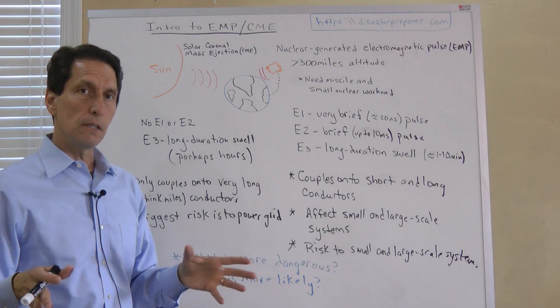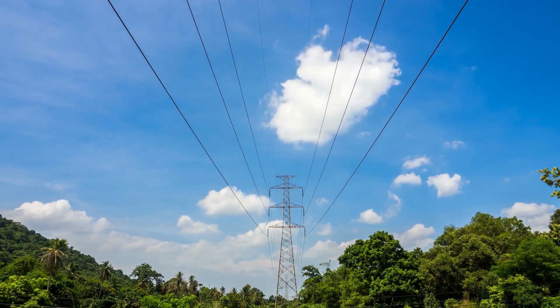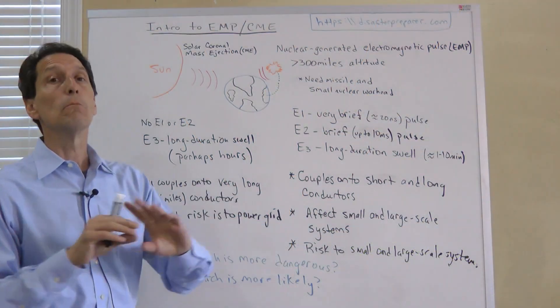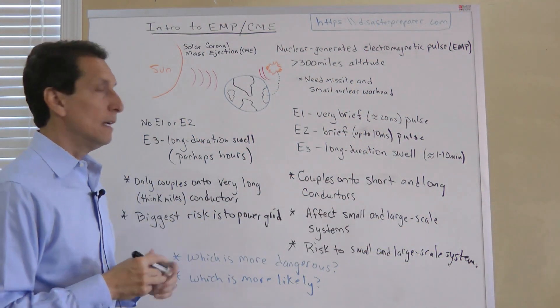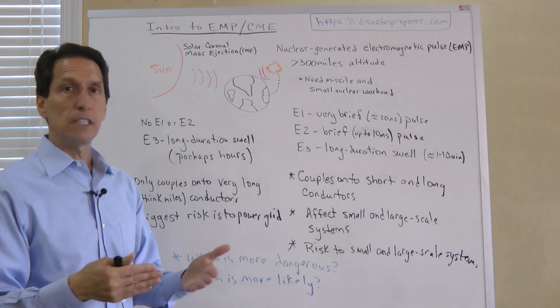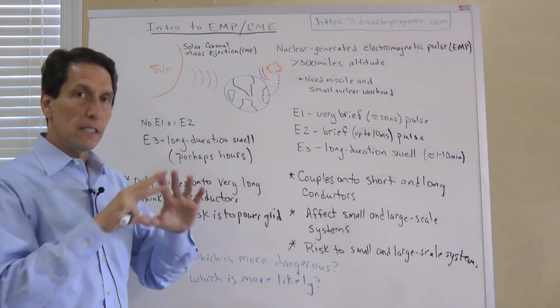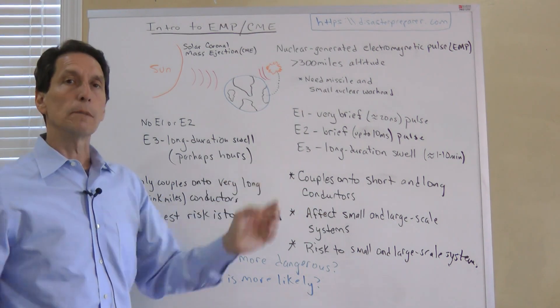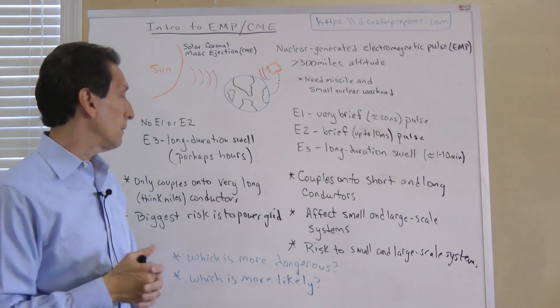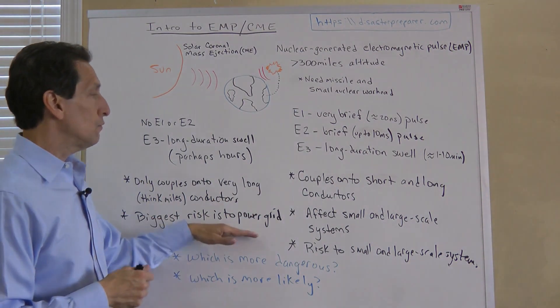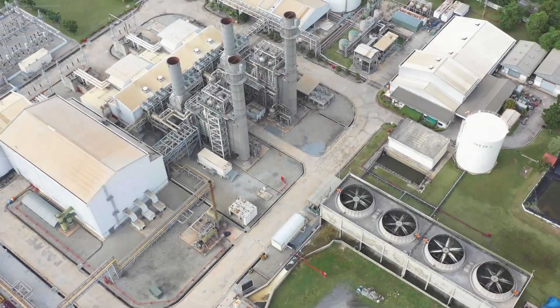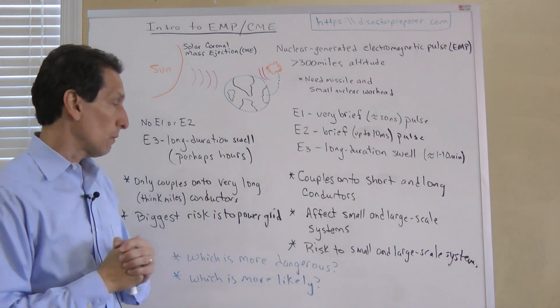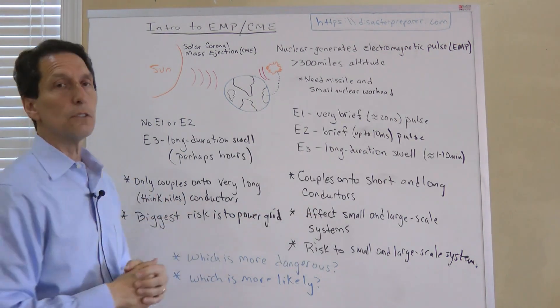The CME only had this E3, so it can only couple into very long conductors. When I say very long, I don't mean like the harnesses in your car. I mean things that are miles long. A CME won't affect anything that doesn't have conductors attached to it that are miles long. But anything attached to the power grid fits right in that. You can couple that energy in there and potentially that energy flows downstream and causes damage to anything connected to it. So the biggest risk from the CME is to the power grid.